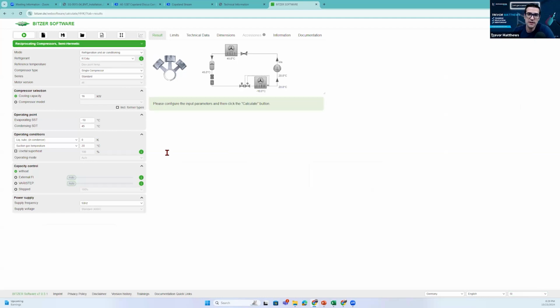You just take out a calculator and use a units converter. If I don't know what it needs to be in Fahrenheit or Celsius, or bar or PSI or kilopascals, or kilowatts versus BTUs, it doesn't matter. That shouldn't stop you from being an awesome technician. It's only units. Okay, so let's dive into something here. We'll just do old school R22. There's lots of those compressors still out there in the field. Let's go minus 35 Celsius, right? Let's do minus 40 Celsius because it's minus 40 Fahrenheit at the same time. So it makes it easier for everyone.